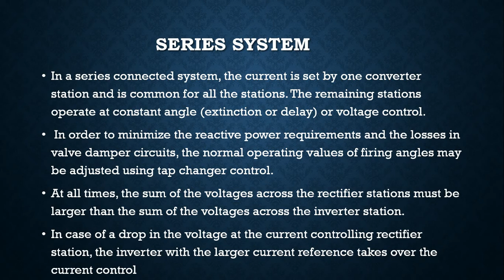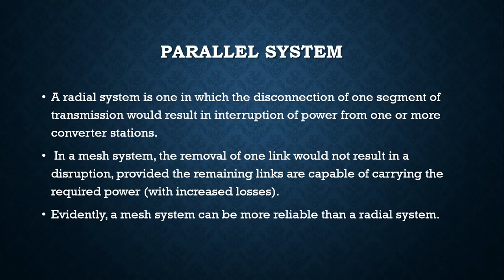As we know, there are two types, a radial and a mesh system. A radial system is one in which the disconnection of one segment of transmission would result in interruption of power from one or more converter stations. In a mesh system, the removal of one link would not result in a disruption, provided the remaining links are capable of carrying the required power, but with increased losses. Evidently, a mesh system can be more reliable than a radial system. So, in many cases, a mesh system is commonly used.